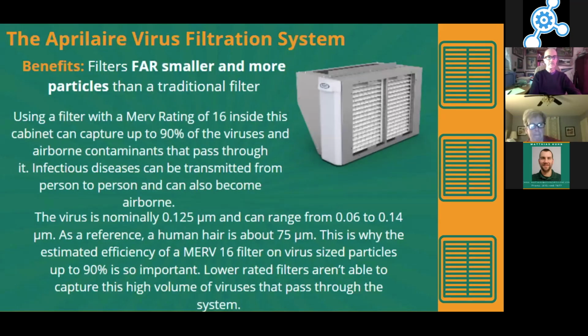So our standard filter, when we install new equipment, is this filter that you see on the right here. This is an Aprilaire filter cabinet. It can accept multiple filters, anything from MERV rating 10 up to that 16 range. And again, that 16 range can capture up to 90% of viruses and airborne contaminants. Viruses are very, very small. As you can see, if you look down, middle of the paragraph, viruses are between 0.06 and 0.14 microns, and the filter will catch about 90% of that. So MERV 16, great filter.